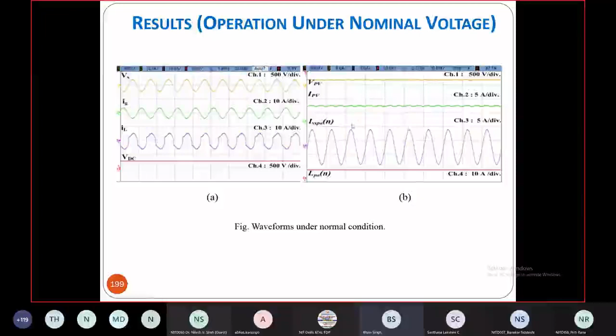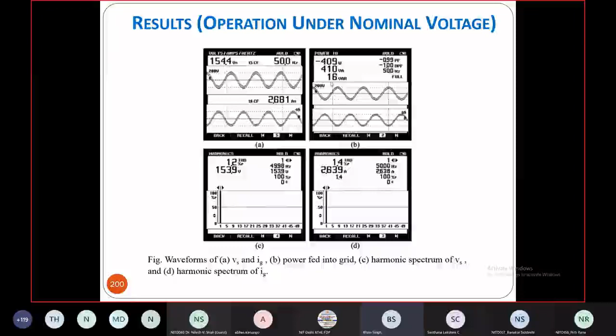That is also because cos 180 is -1, so that is also unity power factor. And the THD we are able to get in current and voltage THD - of course the grid was 1.2%, but the current THD around 1.4%. So reasonably good current THD with 409 watts going to the grid with the small system.